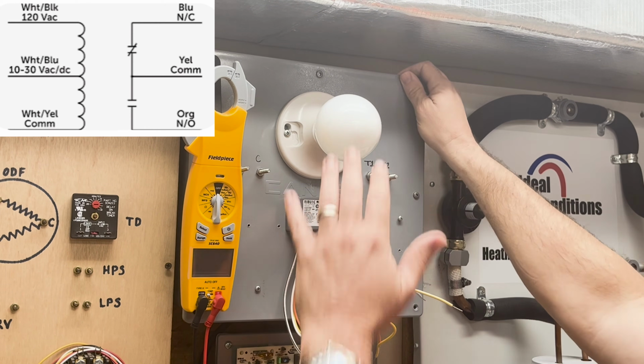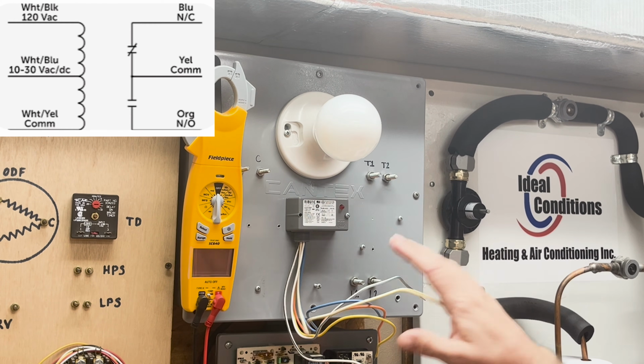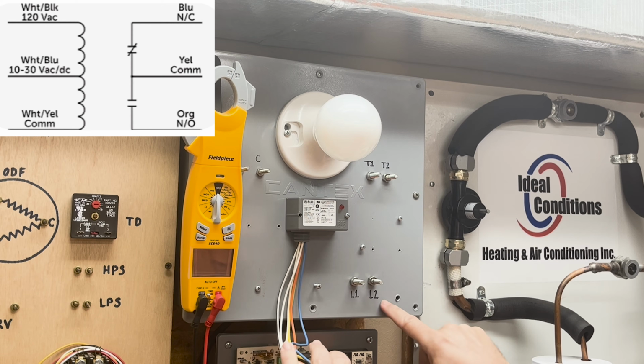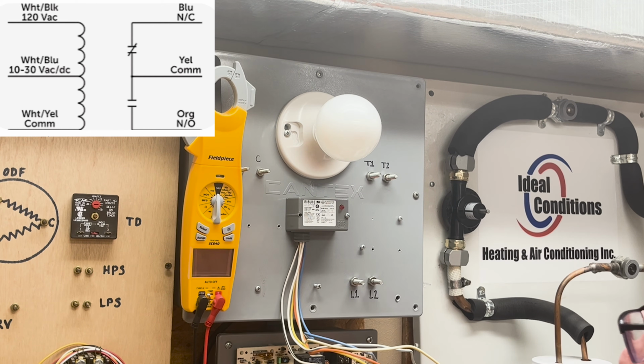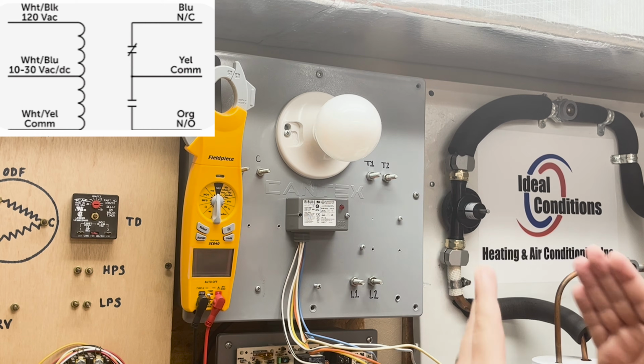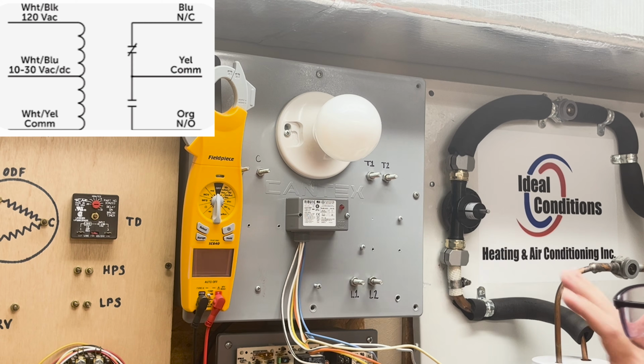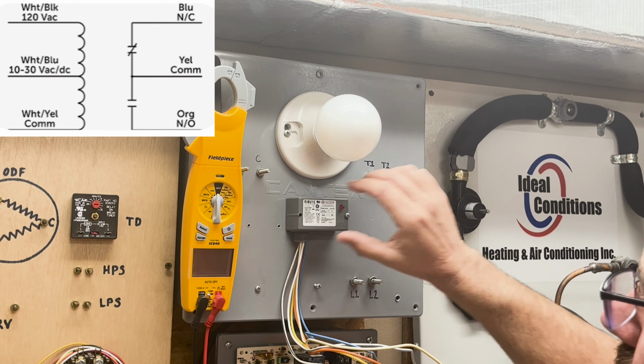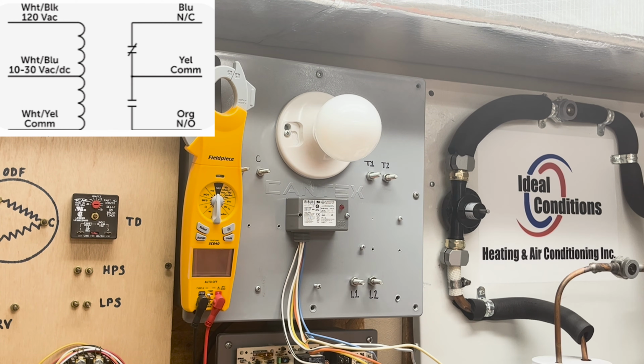At the CANTEX box, we have our light bulb, we have our 24 volts primary, we have L1 and L2 present. L1 and L2 is your line voltage. It's 2 legs of power, so we have 240 volts of electricity. This is danger close, so we can practice using this relay to try to get this load to work, so we don't have to learn in the field as much. At the end of this, we're going to go to a fan motor where we're going to show you how to use this as a blower relay. And then we're going to take it to the smart board and show you how to wire it up step by step. To get started, we're going to go ahead and demonstrate the power that we have.